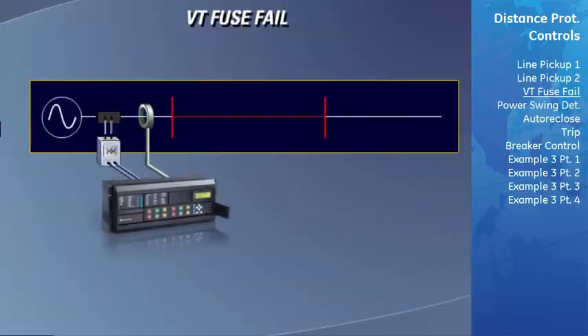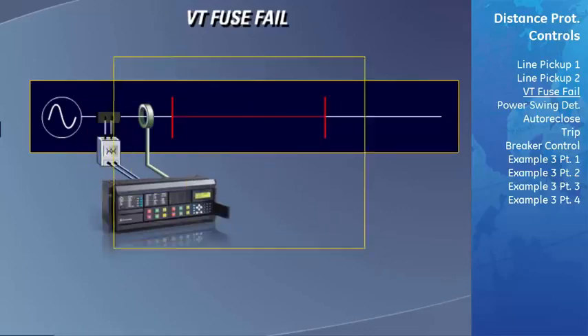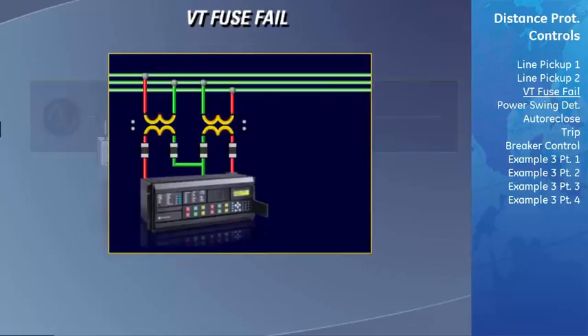In order to calculate the impedance of a transmission line, the D60 must measure the magnitude of the current and voltage on the line. Although the CTs and VTs are often drawn as a single instrument on single-line diagrams, in actuality, there are 3 CT inputs to the relay and 3 VT inputs to the relay, one for each phase of the transmission line. In between each VT and the D60, a fuse is located to protect the secondary devices, such as relays, from being exposed to very high voltage levels.